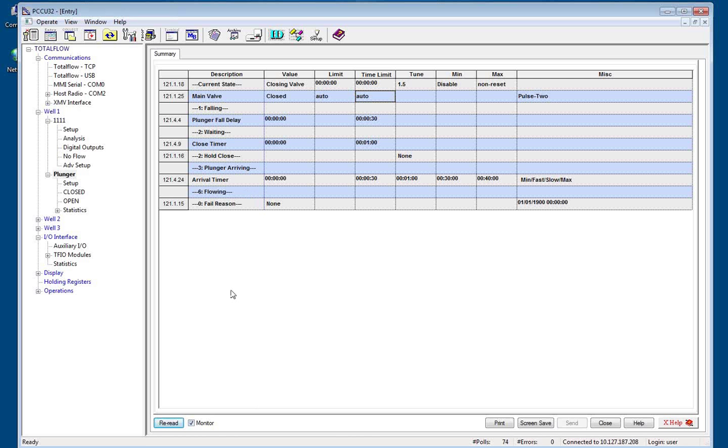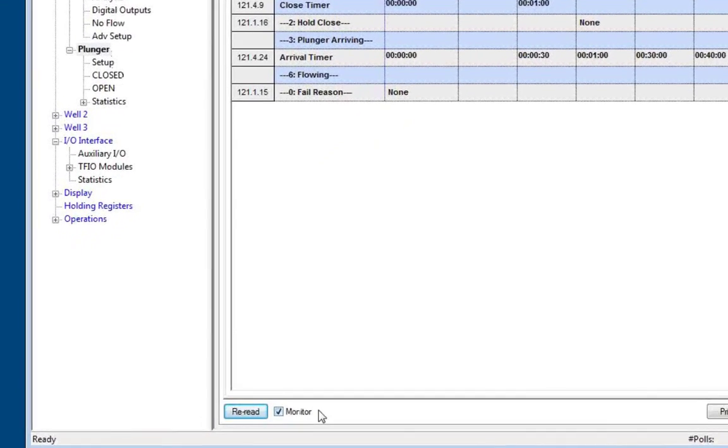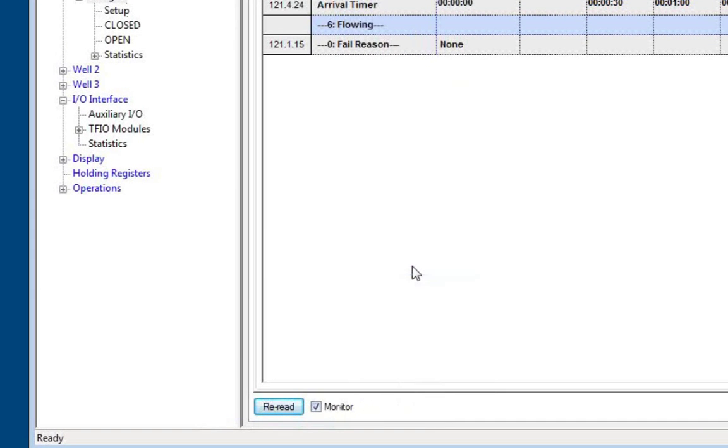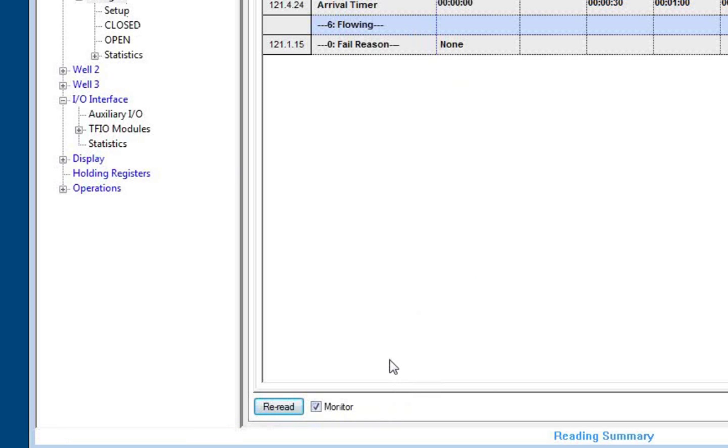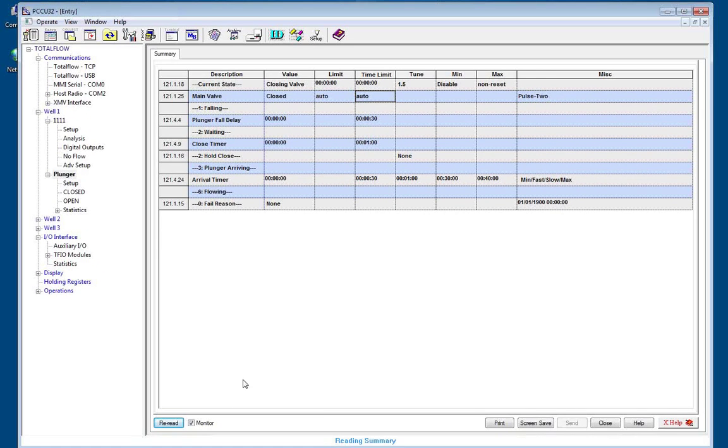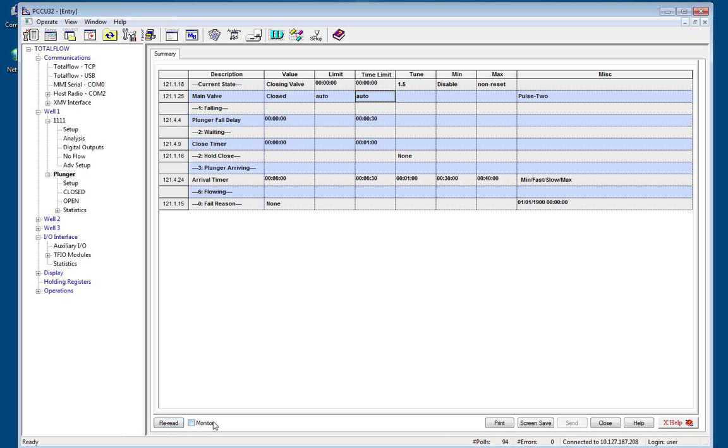One word of caution, as you're going through setup screens in PCCU, if you've checked the monitor button and you have an interval of something like one second, the page may update and refresh before you get your settings entered into the device and are able to send those changes down to the meter. So if you're going to enter settings, make sure that you uncheck monitor and then you won't run into that problem.